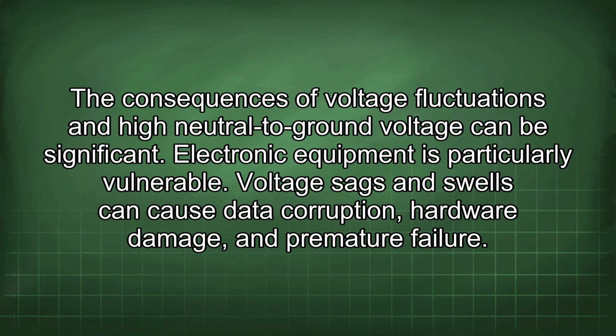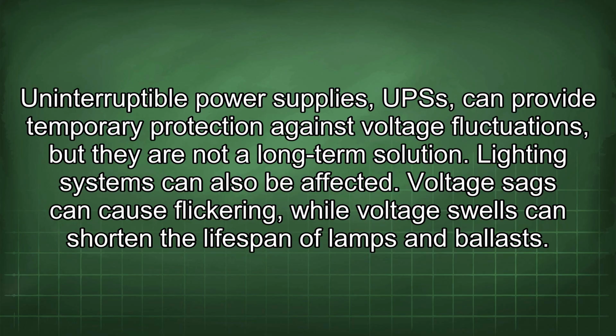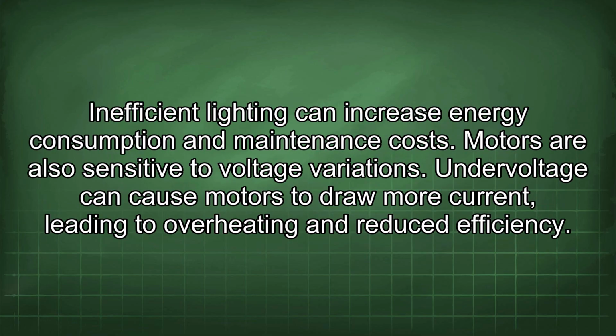The consequences of voltage fluctuations and high neutral to ground voltage can be significant. Electronic equipment is particularly vulnerable. Voltage sags and swells can cause data corruption, hardware damage, and premature failure. Uninterruptible power supplies, UPSs, can provide temporary protection against voltage fluctuations, but they are not a long-term solution. Lighting systems can also be affected. Voltage sags can cause flickering, while voltage swells can shorten the lifespan of lamps and ballasts. Inefficient lighting can increase energy consumption and maintenance costs.